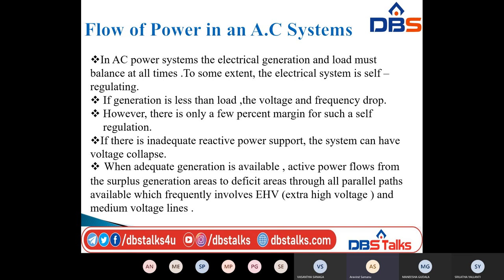In AC power systems, the electrical generation and load must be balanced at all times. If the generation is less than the load, the voltage and frequency will drop. However, there is only a few percent margin for such self-regulation. If there is inadequate reactive power support, the system can have voltage collapse.